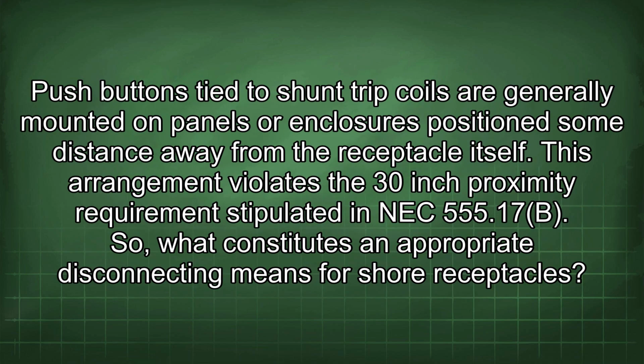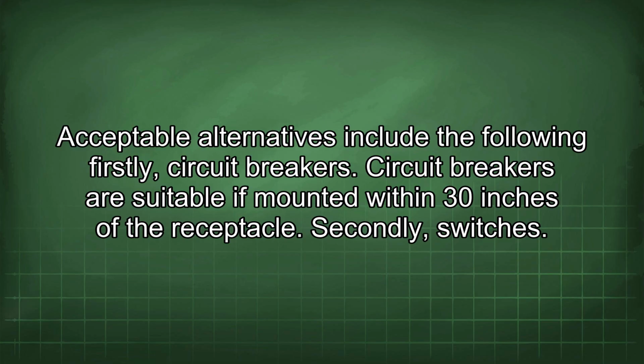Push buttons tied to shunt trip coils are generally mounted on panels or enclosures positioned some distance away from the receptacle itself. This arrangement violates the 30-inch proximity requirement stipulated in NEC 555.17(B). So, what constitutes an appropriate disconnecting means for shore receptacles? Acceptable alternatives include the following.